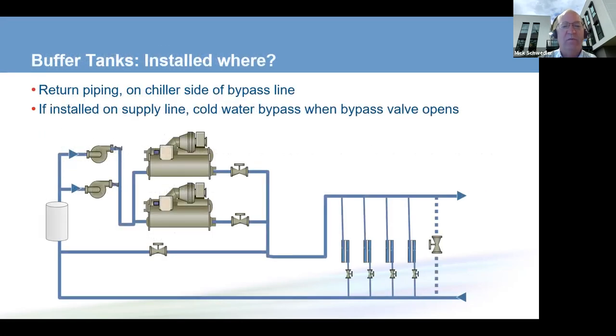But if you don't, where should that buffer tank go to increase the system volume? A lot of times people want to put it on the supply side so that if the chiller goes down or turns off, we still have some cold water going out to our coils. The issue is if we put it on the supply side and this bypass valve opens quickly, the return water temperature to the chillers changes quickly and we again have a short loop. So where we should install it is on the return side of the line and on the chiller side of the bypass line.